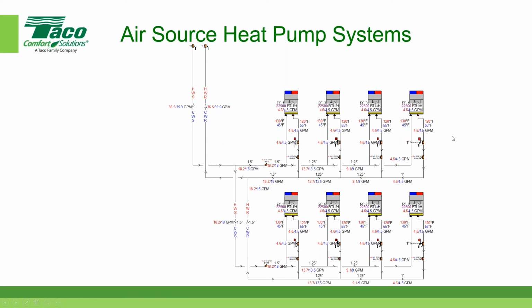These would be the terminal devices. And again, these would be designed for an entering water temperature of 130 instead of the more traditional 180 or 200 degrees. And that's the important thing. You always have to keep that in mind, that you have a lower entering water temperature, so your terminal device has to be selected for 2 things, for a low entering water temperature and a relatively narrow delta T.